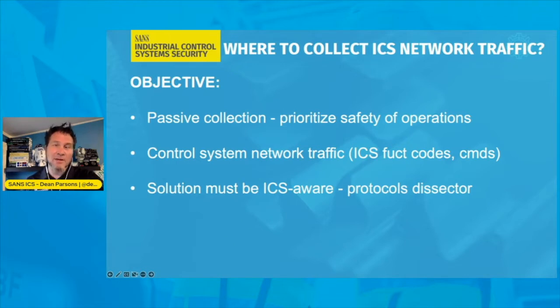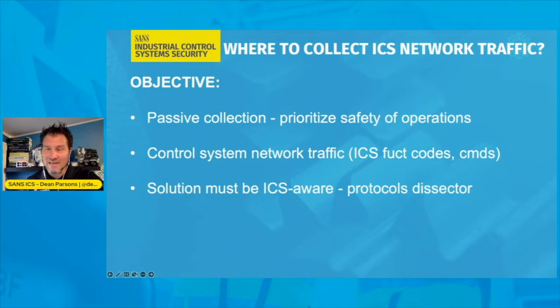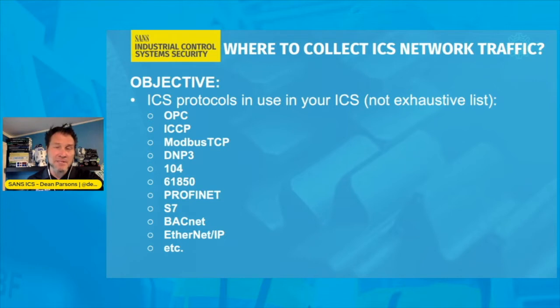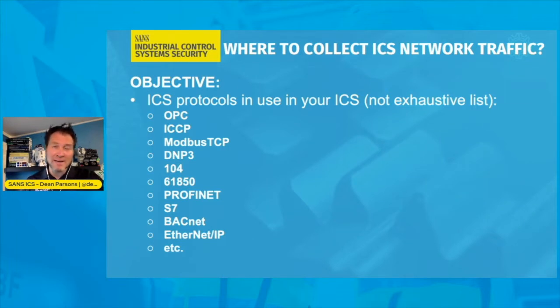At this level, having a solution to capture and dissect what's happening there, you need an ICS-aware intrusion detection system — something that understands and can dissect ICS-specific protocols. These are only a subset of the ICS protocols out there. The common ones are OPC, ICCP, Modbus TCP, DNP3, 104, Goose protocol, and so on. Be sure to check your vendor documentation and equipment deployed to make sure you're collecting and can dissect those specific protocols in your network.